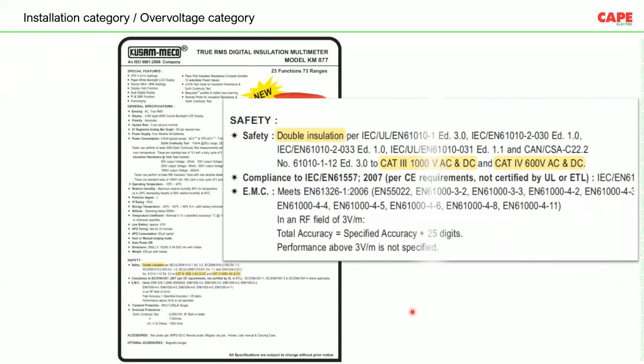This is from Kusum multimeter. You can see here safety, double insulation, and you can see the category here, category 3, 1000 volt AC or DC, category 4, 600 volt AC and DC. What does this mean? This meter can be used in location 3 up to an operating voltage of 1000 volt AC. Similarly, this meter can be used in location 4, that means at the mains incoming, for testing the parameters of a panel board, provided the voltage is up to 600 volt. That means category 4 at 1000 volt is not allowed. So this is how it has to be read.